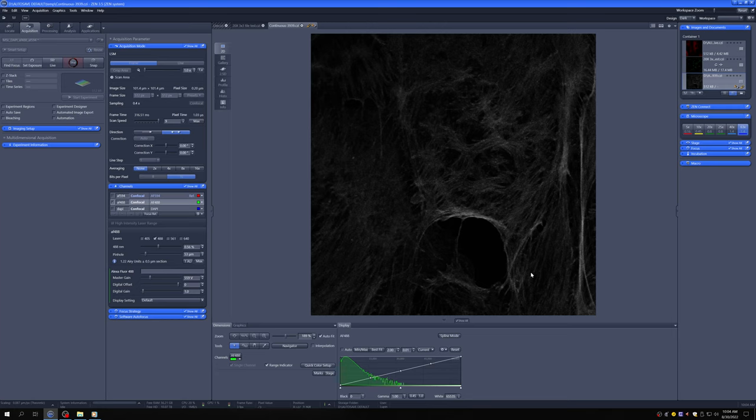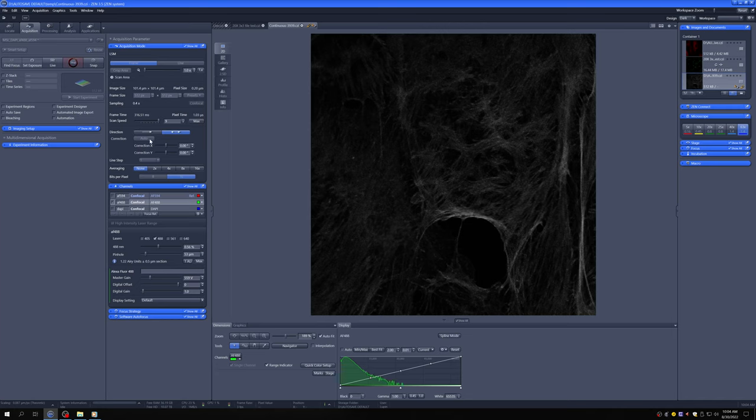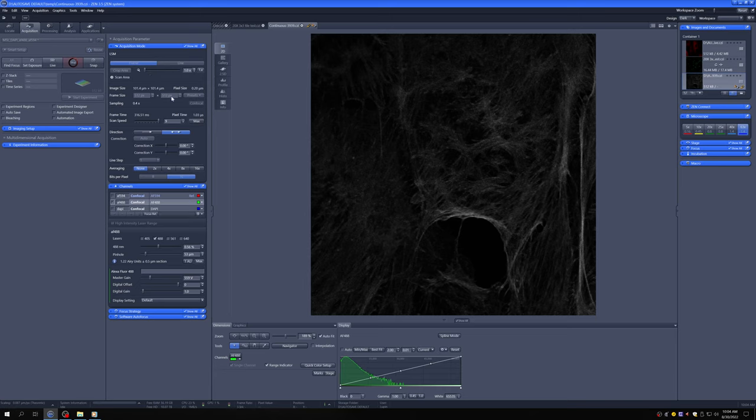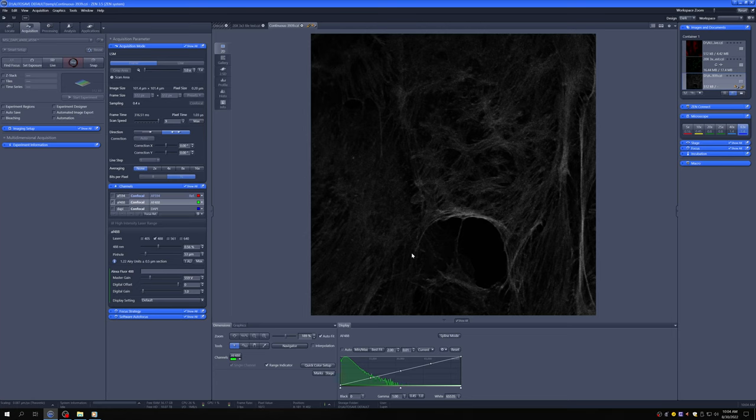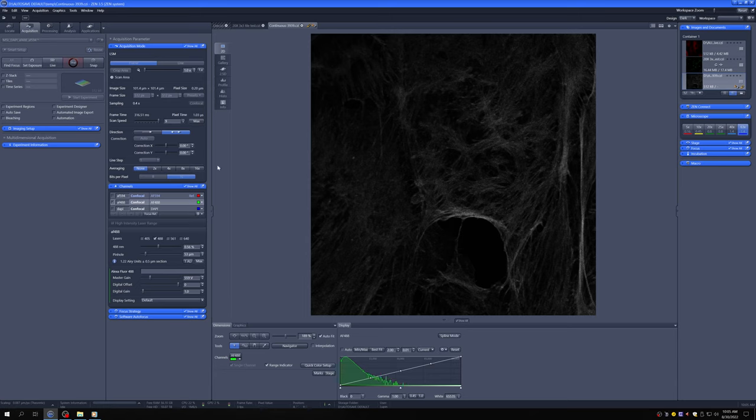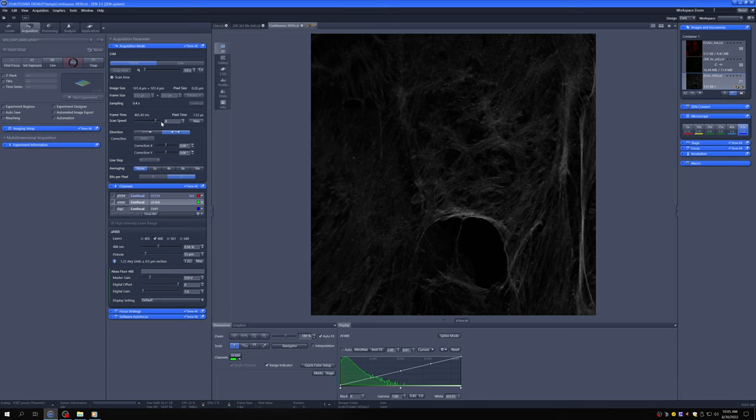Usually these slight imperfections happen when the speed is really fast. Here we're maxed out and we can't really see much evidence of it. But you'll see later when we start playing with the zoom and the frame size that that can adjust the speed a little bit. And there you can see problems start to crop up. If you're in that situation, you may want to consider doing the following. Let's say we were in that situation now, which we're not. You may be able to lower the scan speed a little bit, still have an advantage from the bi-directional.